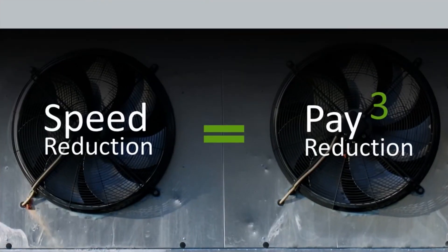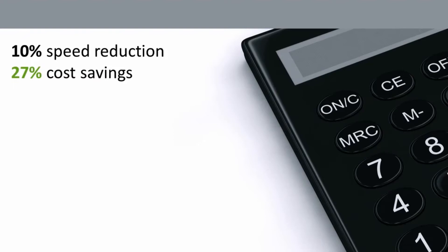The basic concept with VFD savings is that your speed and your flow are more or less proportional, but the energy consumption is cubed. If you are running your motor at full speed or 60 Hz, you don't have any savings, but any reduction pays back the reduction cubed. For example, if you take that oversized motor down to 90% speed, you are at 54 Hz — a 10% slowdown. Your savings is 27%.